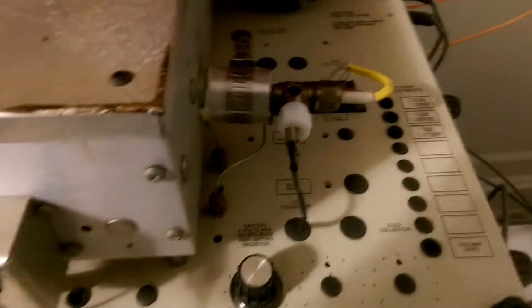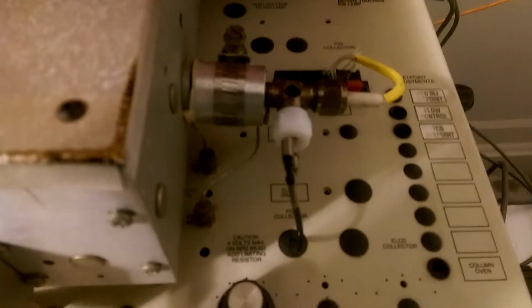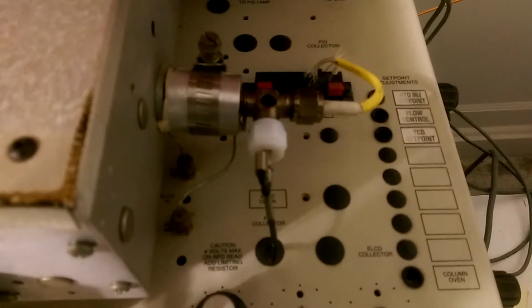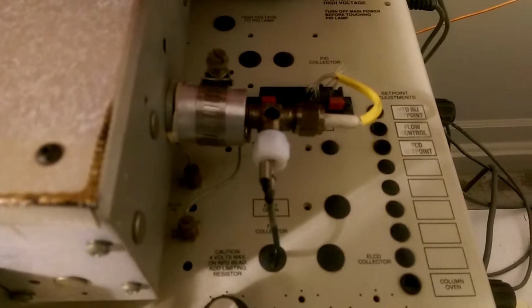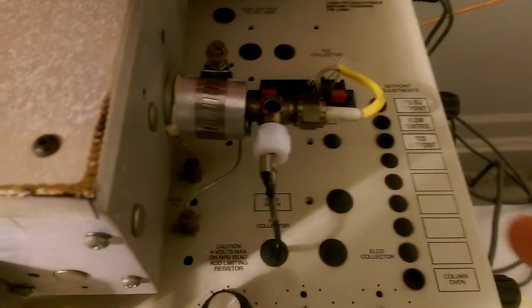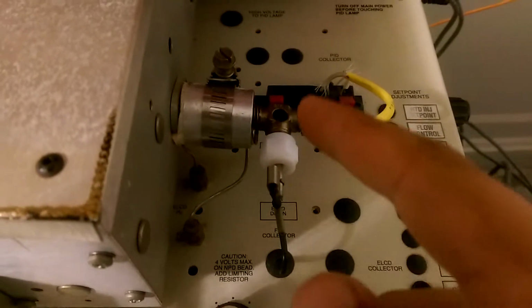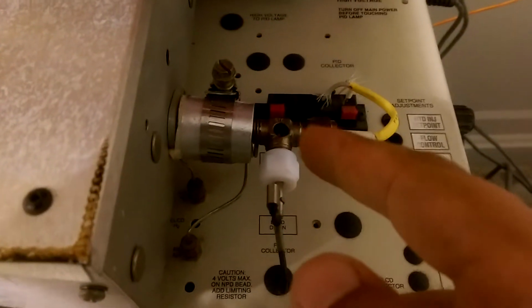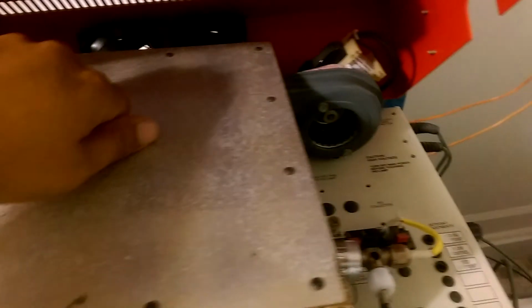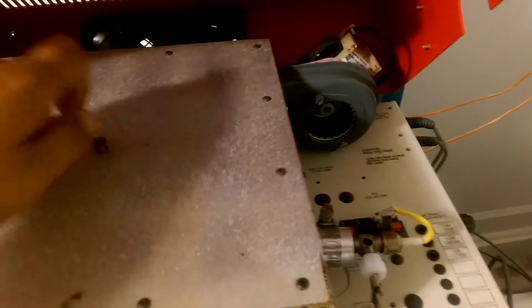Here we also have the FID, the actual FID detector. It's currently on, but here's the collection unit, and this is the vent, the top vent for the FID. This is the unit's oven. Inside the oven we have a column, and also it has a blower on the side for cooling the oven after high temperature use.